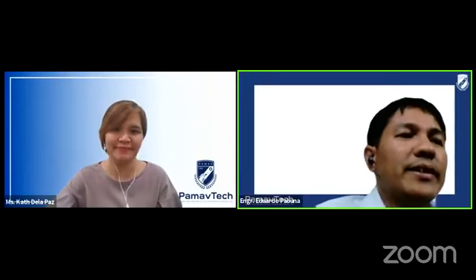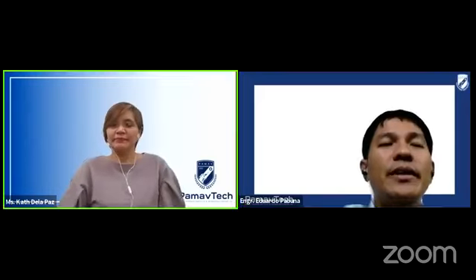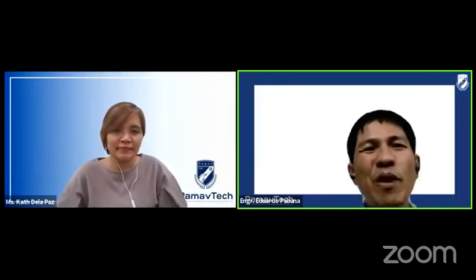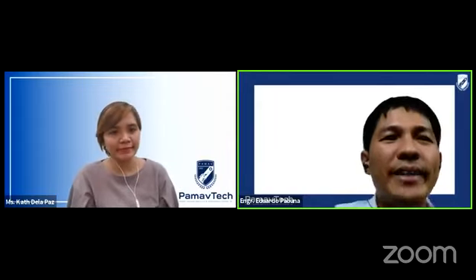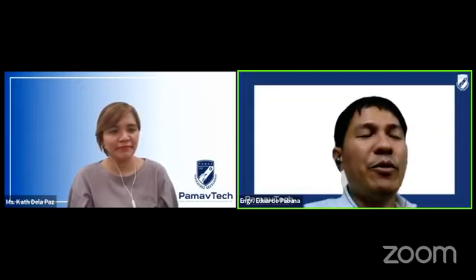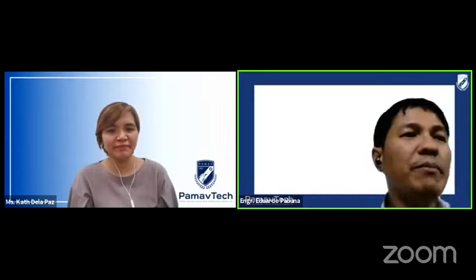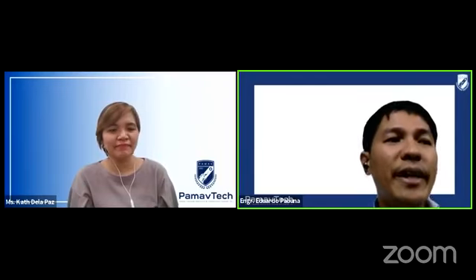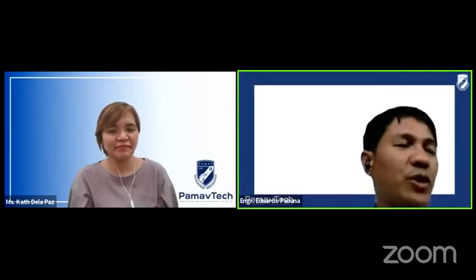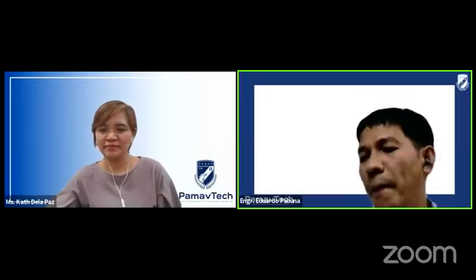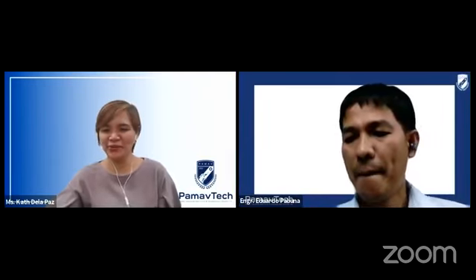I will answer first, Lex. The best time to install an active filter is when your plant is already in operation. Because in the design, it is only design, but we don't know how the equipment behaves. If you have a lot of equipment that produces harmonics, it's not easy. We can run a harmonic analysis in the software, but that is only a simulation. So in my opinion and experience, we usually install during operation. Lex, you can add. No more to add, sir. Okay, there you go.